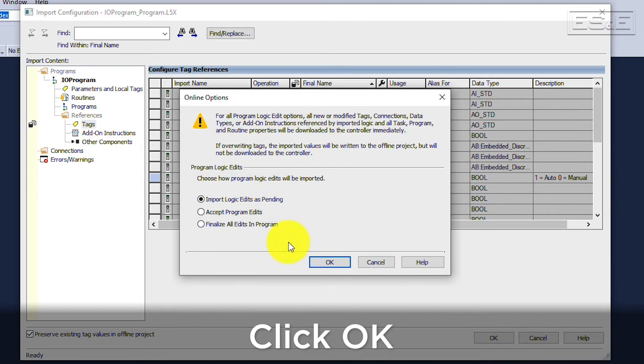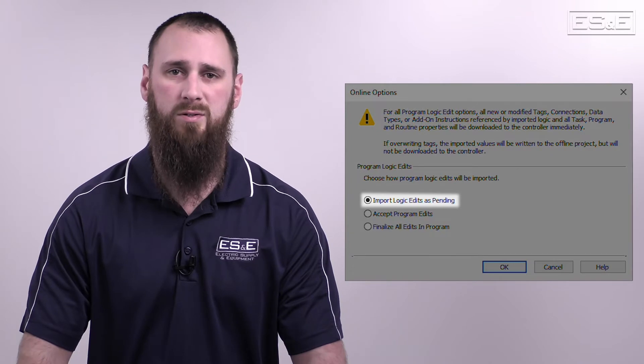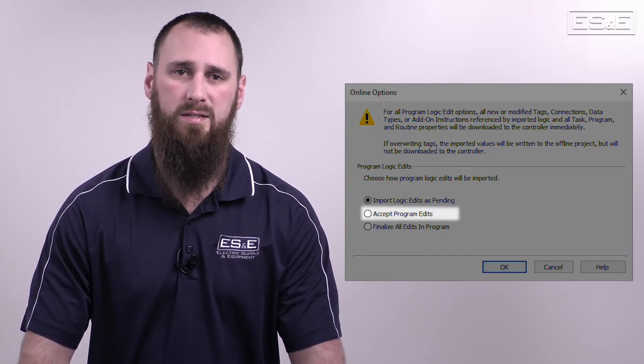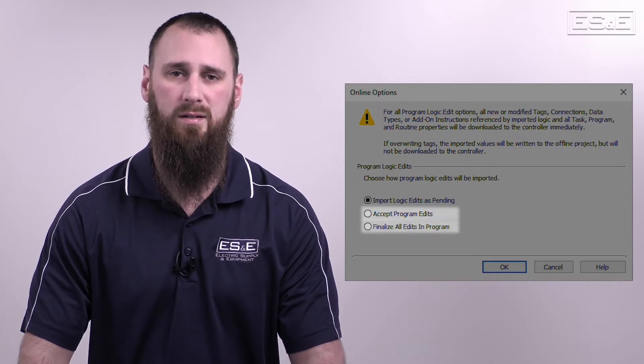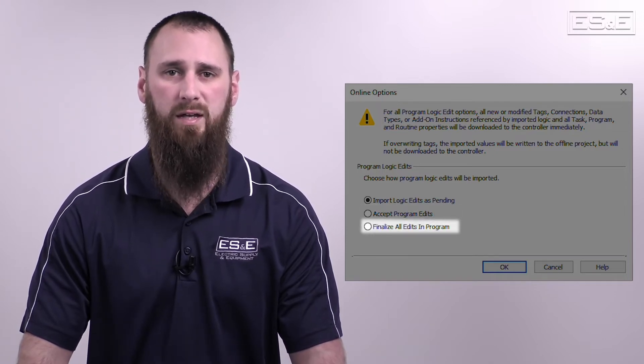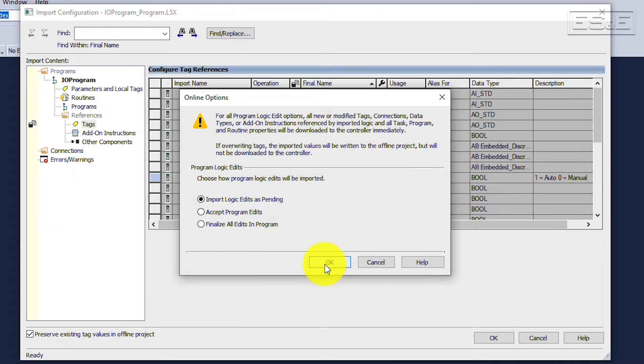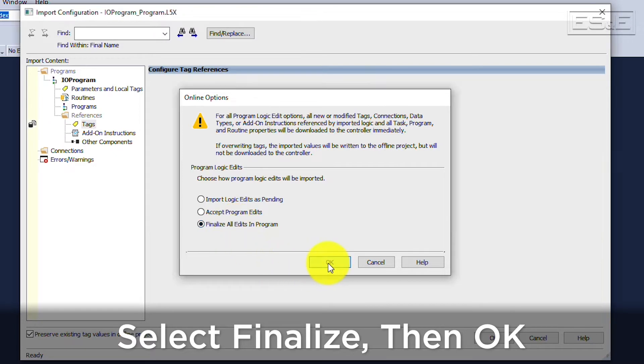When you click OK, another window appears allowing you to import everything as Pending, Accept Program Edits, or Finalize All Edits. Pending allows you to verify code without running it; Accept Edits tests the code but allows you to stop edits; and Finalize fully implements the code into the controller. This is the test environment and I know it's OK, so we are going to Finalize All Edits.